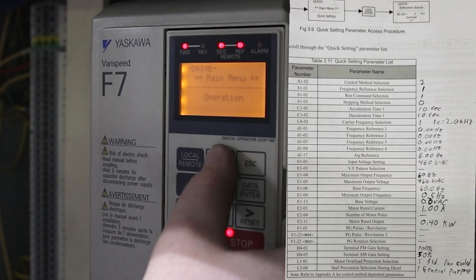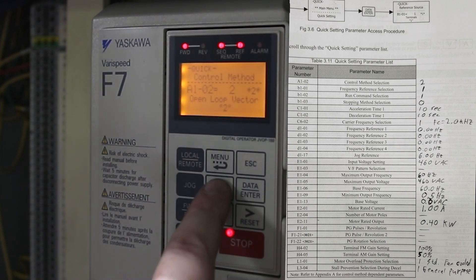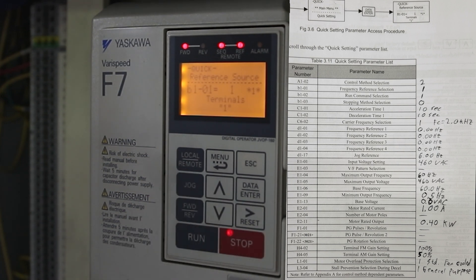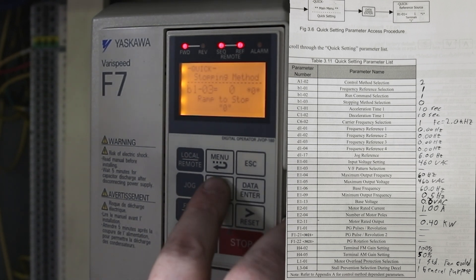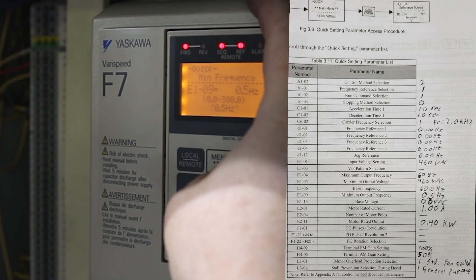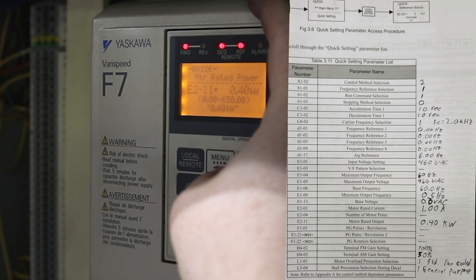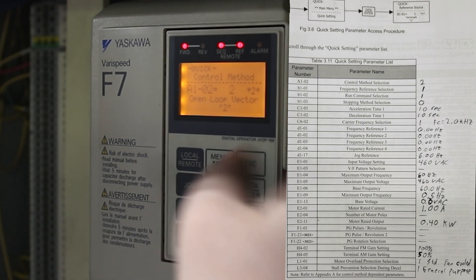I'm going to hit menu, menu, and enter. We're at A102 — that one needs to be a 2, and it already is. Hit up, that goes to B101, which should be a 1. B102 should also be a 1. B103 is at 0, 10 seconds. D117 should be at 6. E101: 460 volts is right, 60 hertz. E109: 0.5 hertz, 0 volts, 1 amp, 0.4 kilowatts, 100%, 50%, 1, and 1. All of these settings are correct.